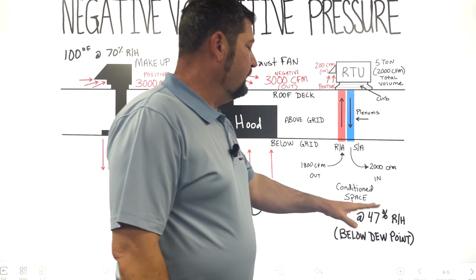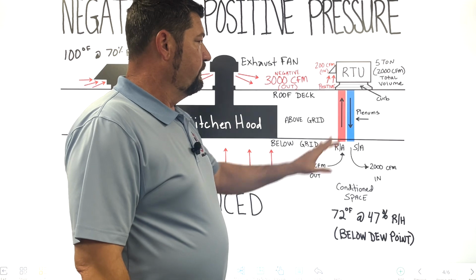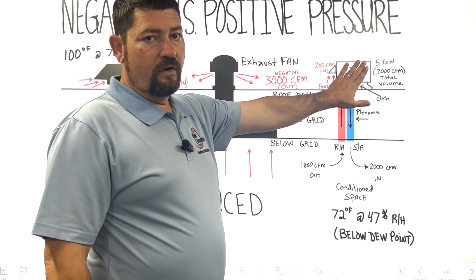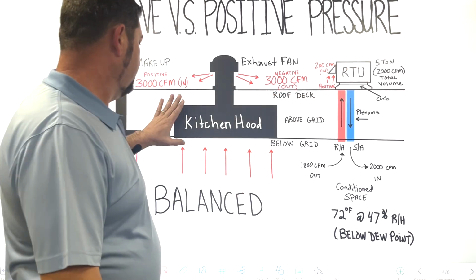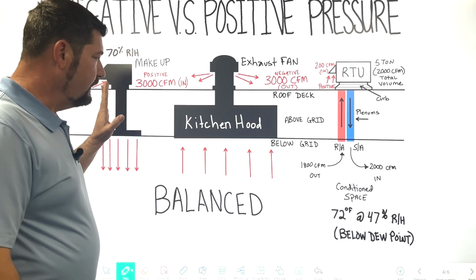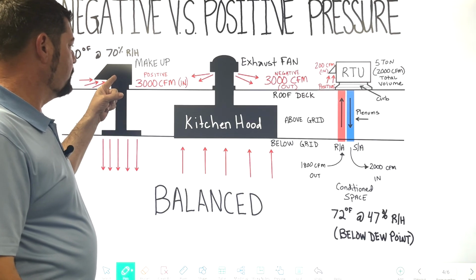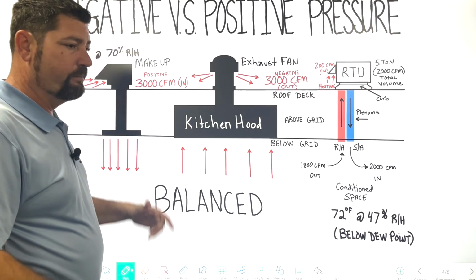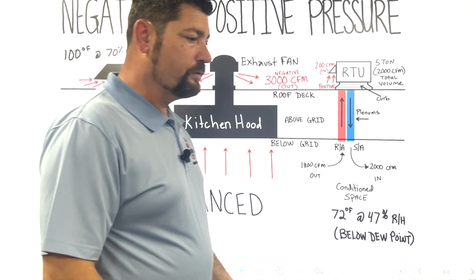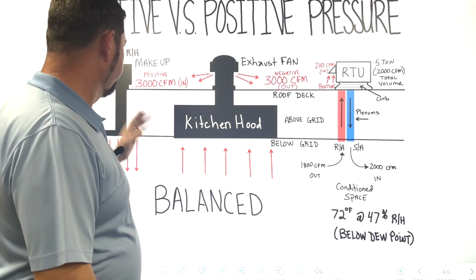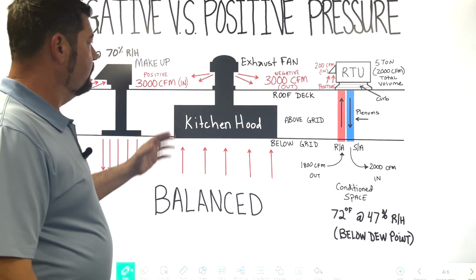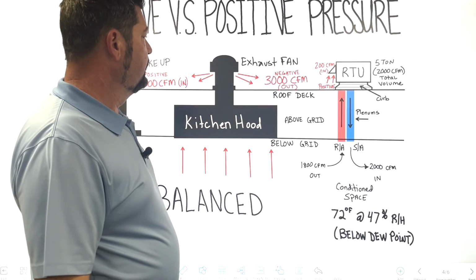You need to understand that if you have a negative pressure, don't start looking at your RTUs. You need to come right back to that kitchen, and you need to make sure that this is turning at the proper RPMs. Make sure the belts are tight. Make sure the motors are spinning. Make sure the wheels are turning and you're pulling in air. Make sure that this exhaust fan is good to go.